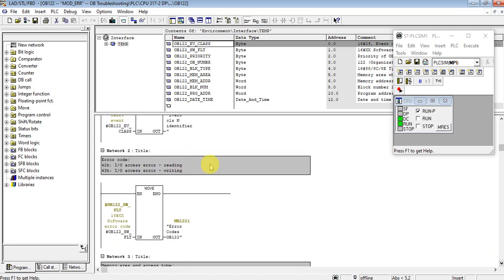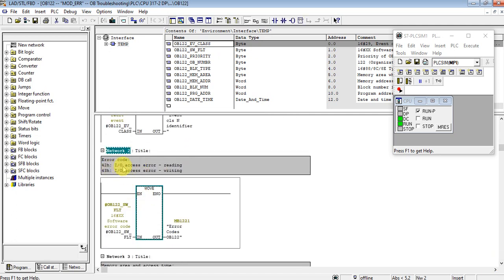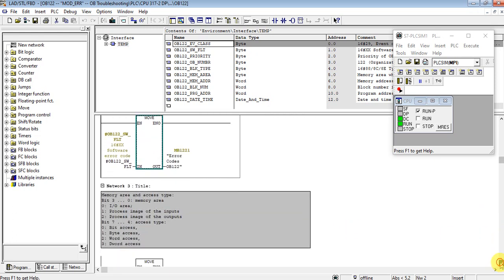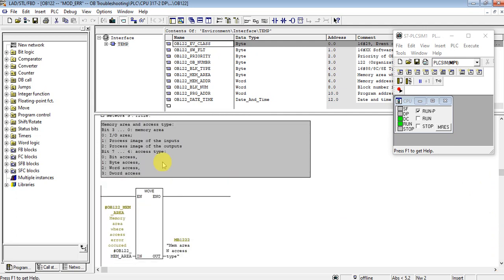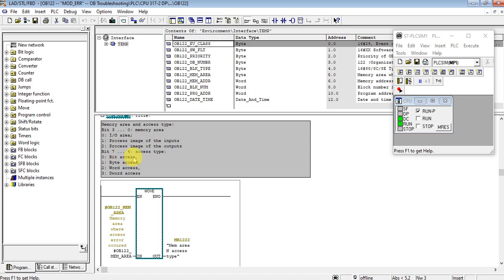On network 2, it will show 0x42 for input module accessing and 0x43 for output module accessing. On network 3, the lower bits indicate the area: 0 means IO area, 1 means process image input, 2 means process image output. Bits 4 to 7 indicate access size: 0 is bit, 1 is byte, 2 is word, 3 is double word.